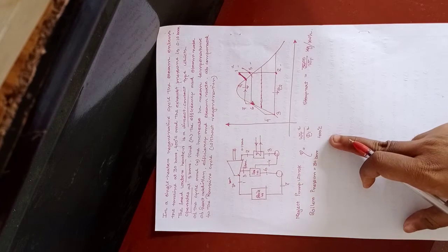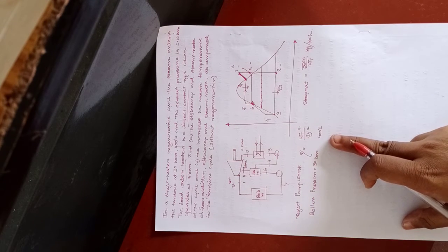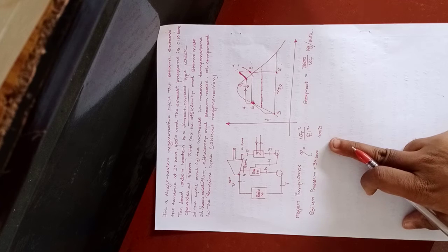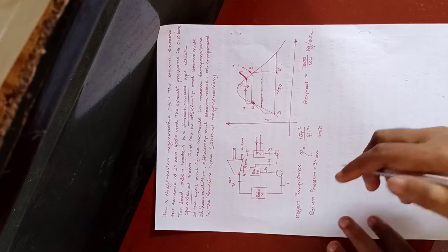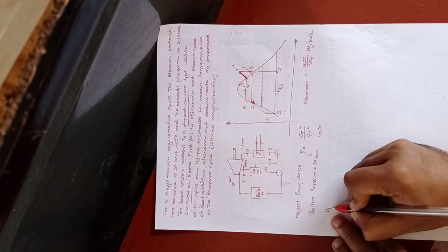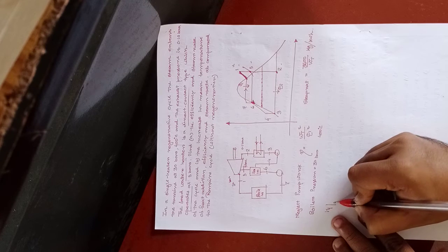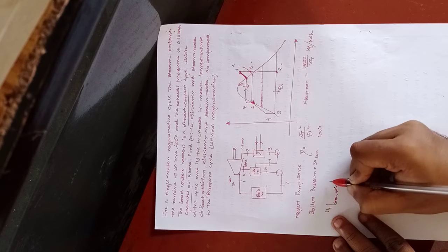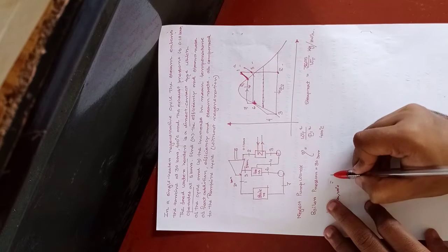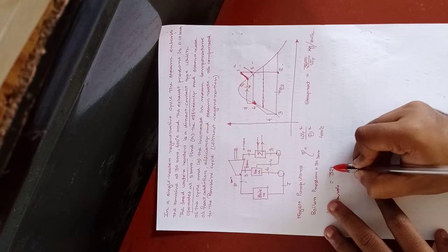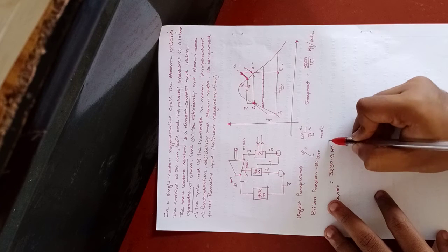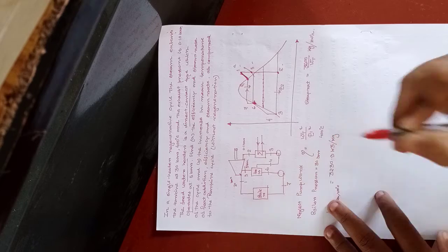From the steam table, we understand that at 30 bar the steam is superheated. So we will find out the condition at 1. H1, at 30 bar and 400 degree centigrade, from the steam table is 3230.9 kilojoule per kg.